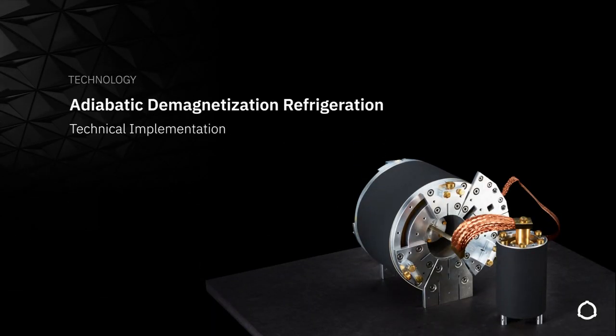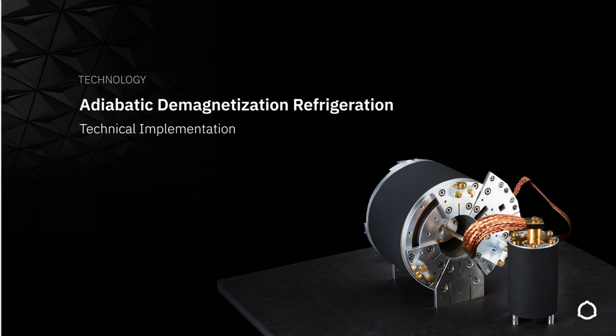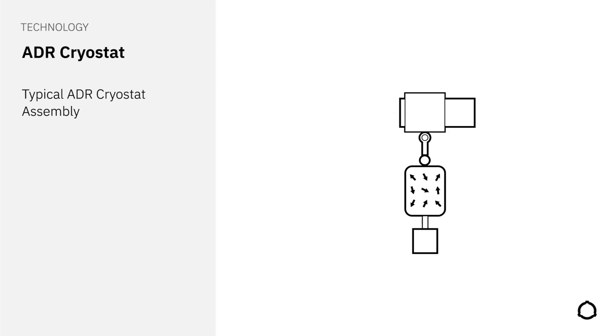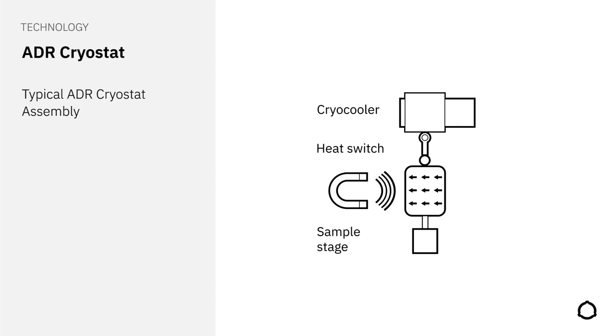Now, let's have a look at how ADR is technically implemented to build a sub-Kelvin refrigerator. In a cryogen-free setup, we use a closed-cycle cryocooler to provide a main thermal bath of about 4 Kelvin. It will be used to pre-cool our ADR cooling medium to a temperature where the total entropy of the material is dominated by the magnetic entropy, this is the contribution of the spin subsystem. The cooling medium is connected to the cryocooler through a heat switch on one end and to the sample stage that contains the experimental setup on the other end. Finally, the medium is surrounded by a superconducting magnet, which allows us to magnetize and eventually demagnetize the medium during the ADR process.